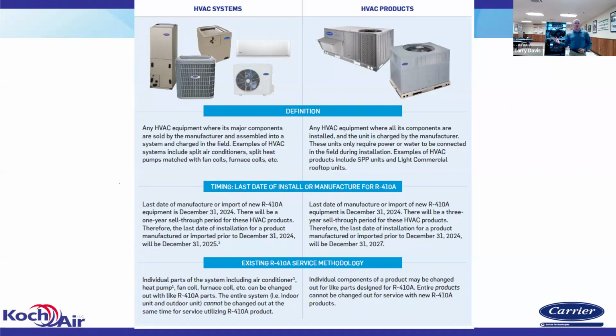If you have an evaporator leak, you can change the evaporator out and put back in a 410A evaporator. But you can't do both of them at the same time. If you do both of them at the same time, that's considered installing a new system, and you have to go with the new refrigerant. Okay. On the package units, you can replace any component inside that package unit and move right along. If you have a compressor failure in a package unit next year, you don't have to change the whole unit to a new 454B unit. You can replace that component. 410A refrigerant is still going to be manufactured. It isn't like when we transitioned from R22 to 410, where 22 had a phase out date. Currently, 410A is going to continue to be manufactured, so it should still be available.